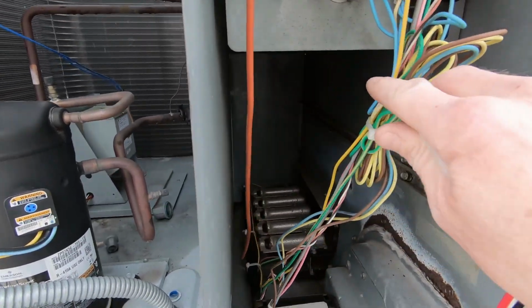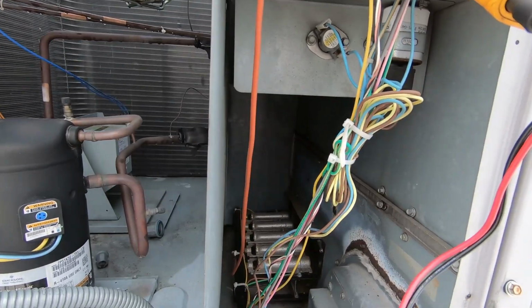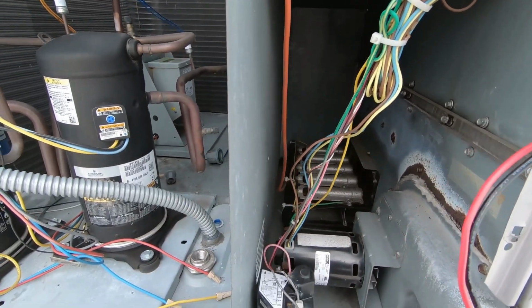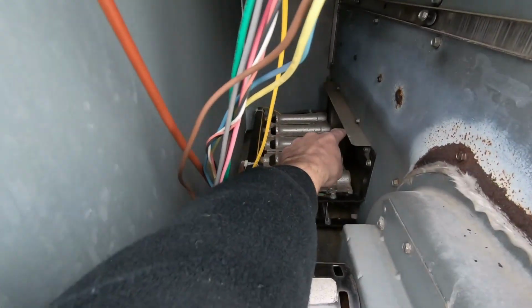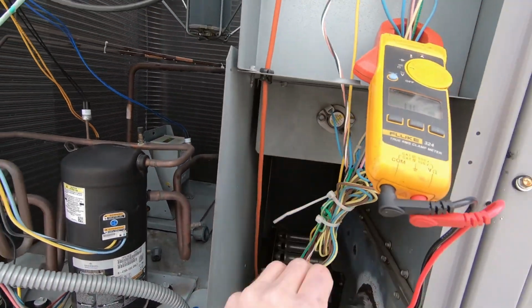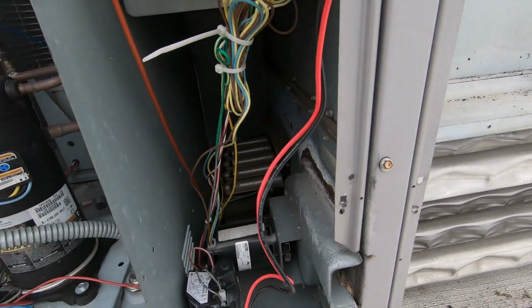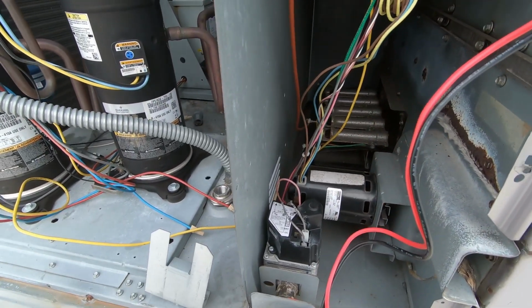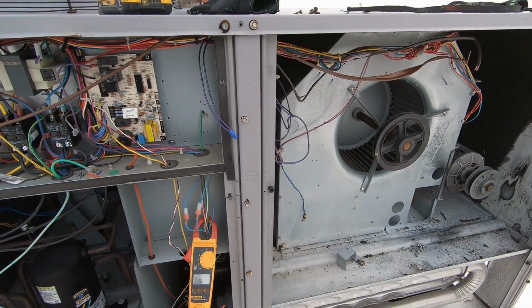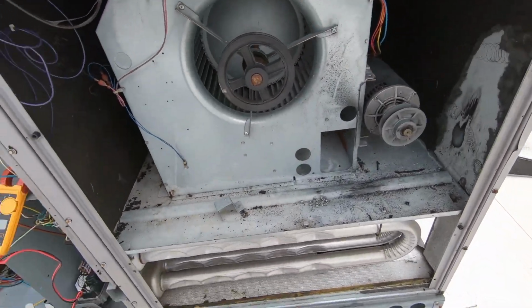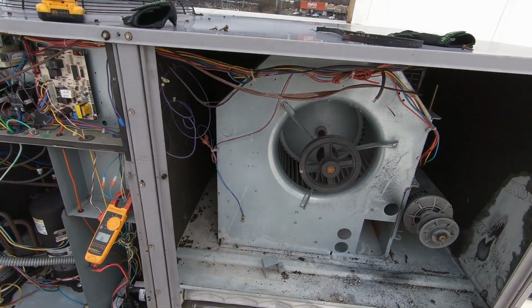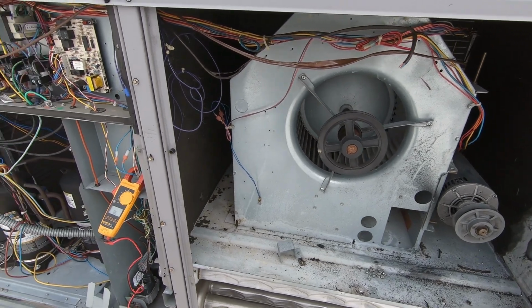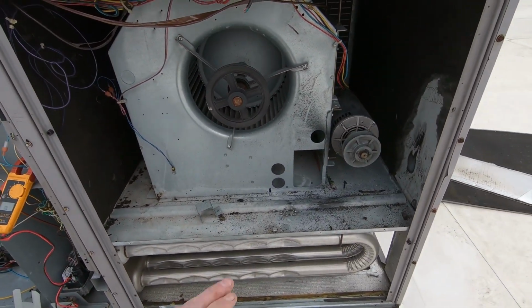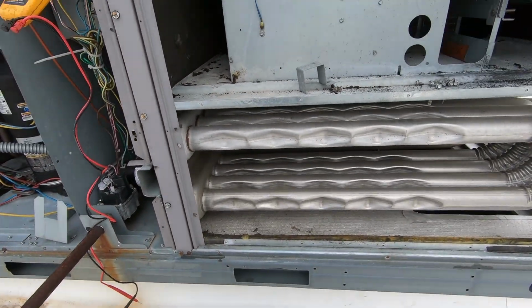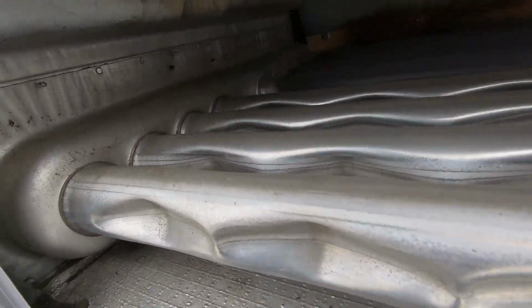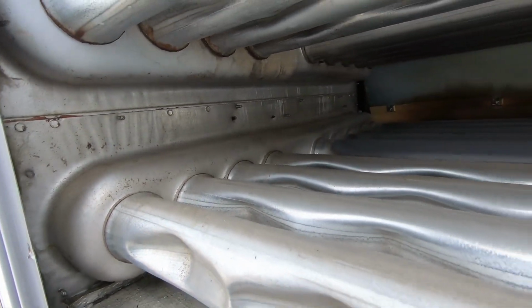Here's your rollout, which I always thought was odd for these carriers, that the rollout is so far away, but apparently it works. I normally see rollouts way up here, but this is the rollout for the carrier. That is the high limit, and it's bypassed, and it almost bit someone in the ass, and it could have possibly caused an even more serious problem than we have here today. So guys, I know I probably don't have to tell a whole lot of you, but if you're watching this video, don't ever think about bypassing a safety switch, limit, rollout, anything.